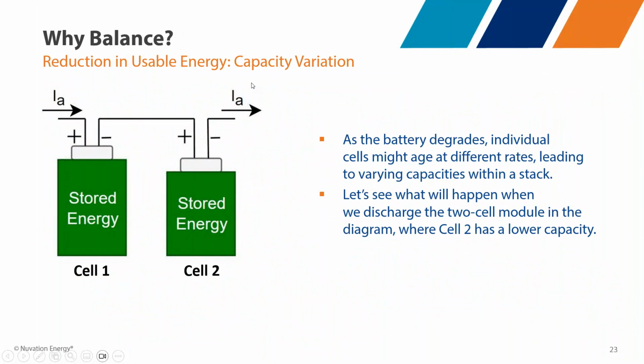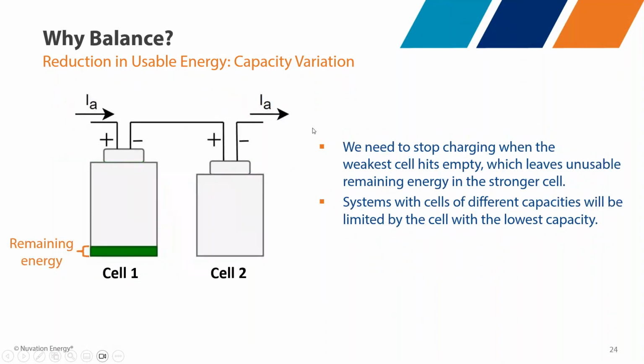As the battery degrades, individual cells might age at somewhat different rates, so you get varying capacities within a stack. Let's see what happens when we discharge this two-cell module. Now cell 2 is drawn slightly smaller, it's got a slightly lower usable capacity, its state of health is a bit lower. So we discharge the system, and cell 2 is now fully discharged, whereas cell 1 has a little bit of remaining energy that we've been unable to gain access to.